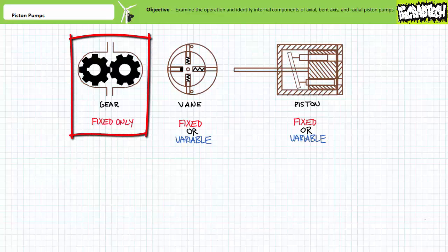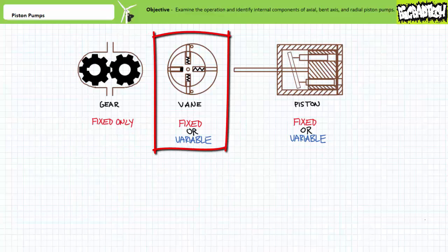Gear pumps use a pair of equally sized meshing gears to provide pressurized flow to a hydraulic system. All gear pumps are fixed displacement pumps. Vane pumps can either be fixed or variable displacement pumps depending upon construction. A vane pump uses a slotted rotor and extendable vanes that scrape the inside of a cam ring.